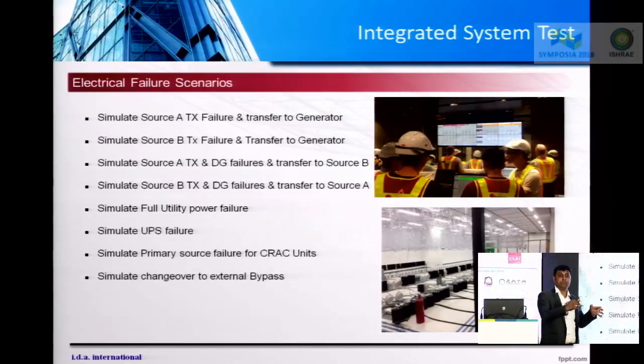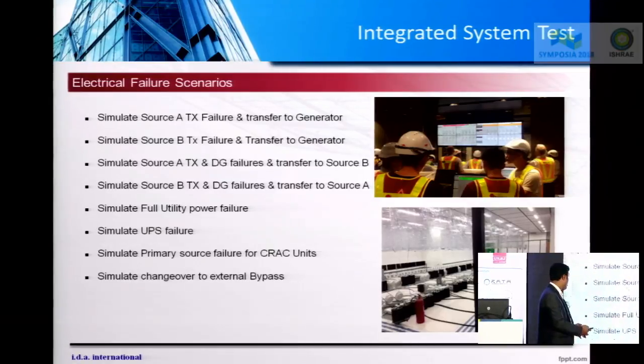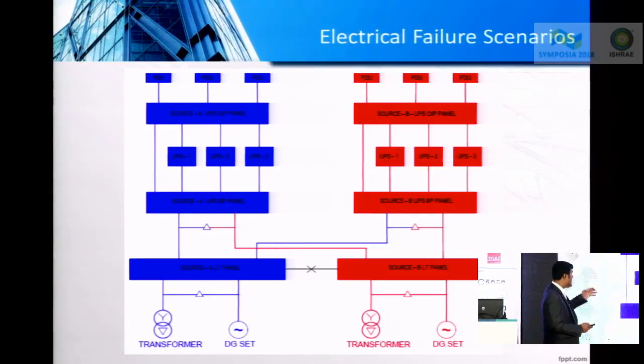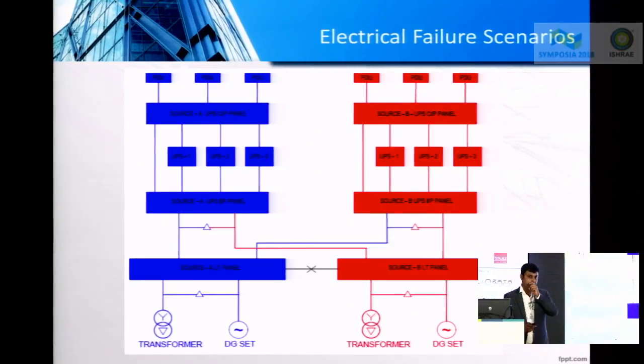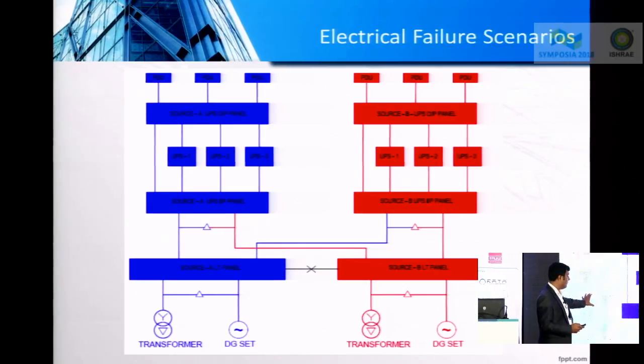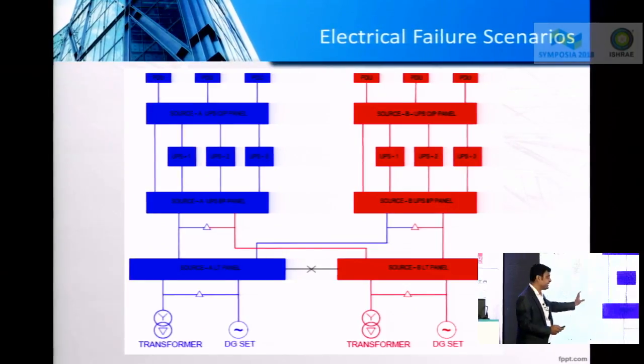We can fail the primary source of the cooling units, and also try to simulate the external bypass changeover. Now let's see how we do it. Now we have a scenario. We have an electrical schematic here that shows source A system and source B system. Each of these systems has its own independent transformer and its own independent DG set.